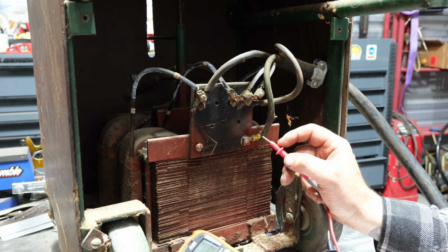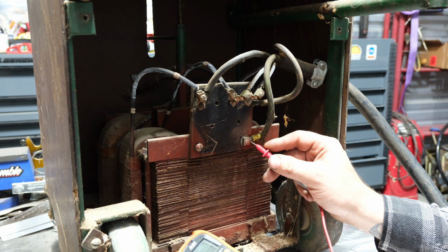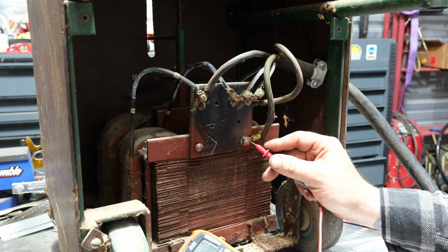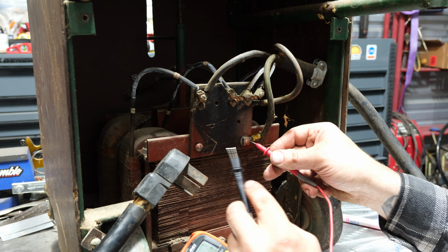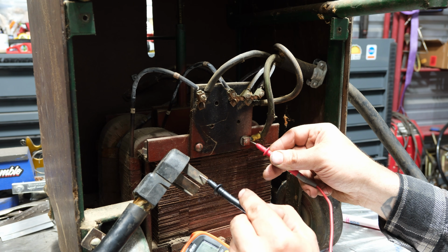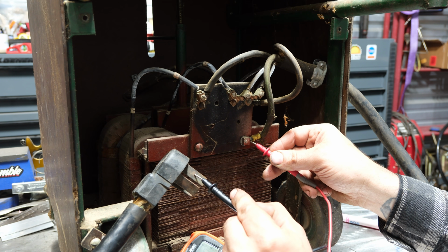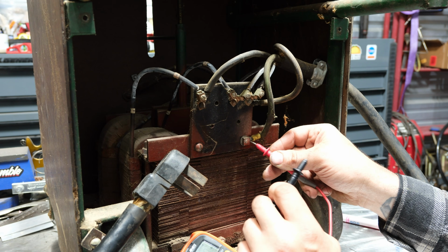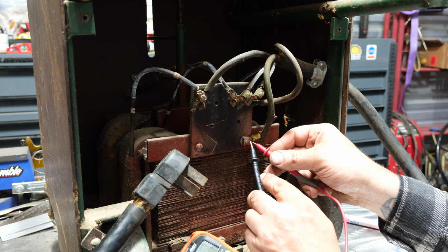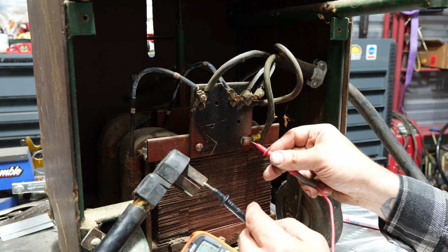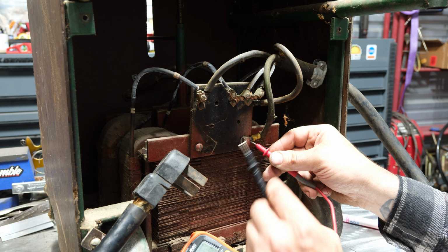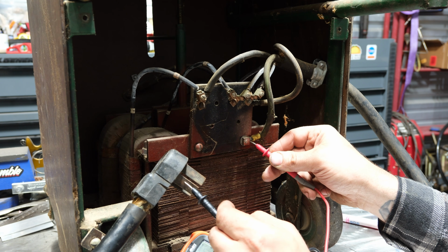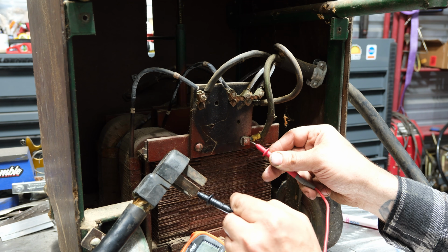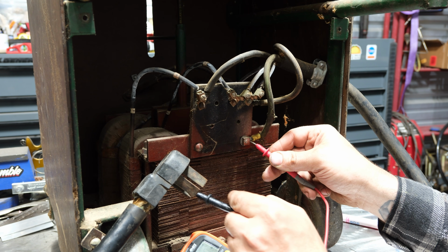That should on the plug go to the green ground, and I'm going to test that here. So now that I have the plug up here, I'm going to check the ground plug, which is this guy right here. And I do have continuity between the ground plug and this. That's good. I'm going to check if I have continuity between the ground and either hot wire. That one I don't. And that I don't.